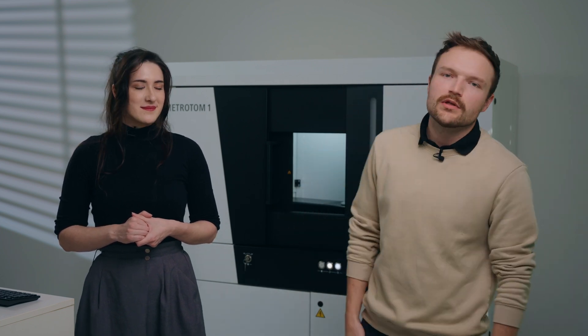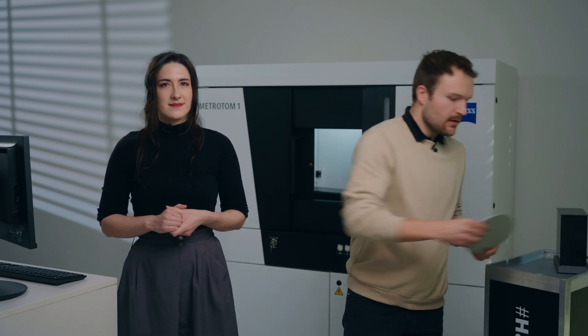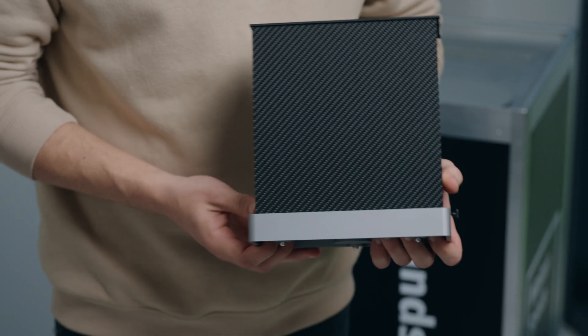First let's take a look at what comes with your system. Of course the first thing you'll notice is the 3D scanner sitting in your measuring room. The Metrotom 1 has a small footprint and is roughly 1.8 meters tall, 1.8 meters wide, and a compact 870 millimeters deep. This means the system can be installed through standard double doors very easily. Your system will also come with several fixturing plates for placing scanning items into the system, as well as a calibration object.